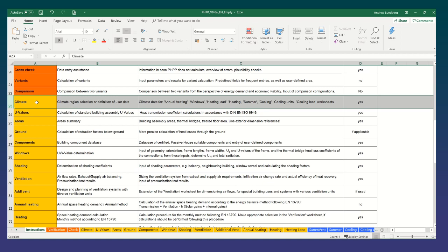When it comes to other certain things for certification like primary energy, normally there's no problem there whatsoever. Passive House still has a limit for primary energy of 120 kWh per square meter per annum. And we'll look at that in more detail later on. So it's a very high value compared to the kind of values we're used to speaking about now in dwellings, especially with NZEB for example, across Europe and the targets we have for NZEB in Ireland. Although just to warn you, you cannot directly compare primary energy values for BERs with primary energy values from PHPP because they're not based on the same thing. However, 120 kWh per square meter per annum is still quite high and often easily achievable, especially then with the use of renewable inputs, which PHPP can also account for in many cases.